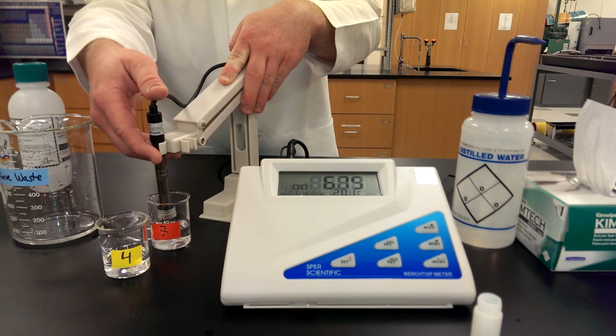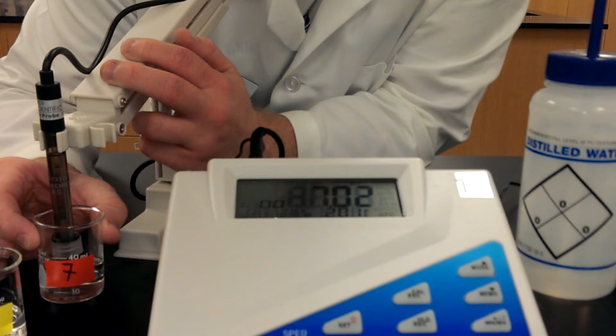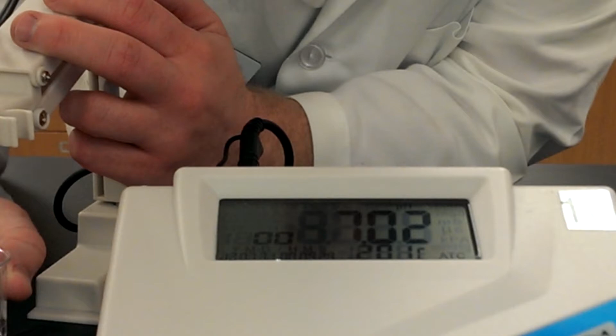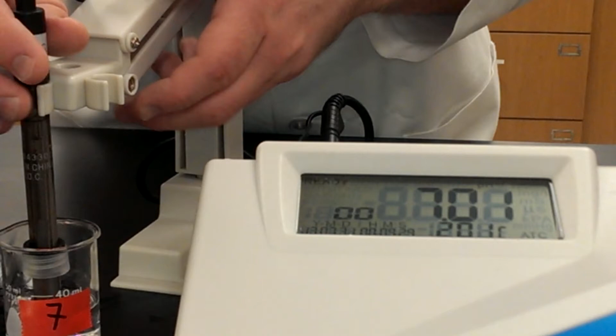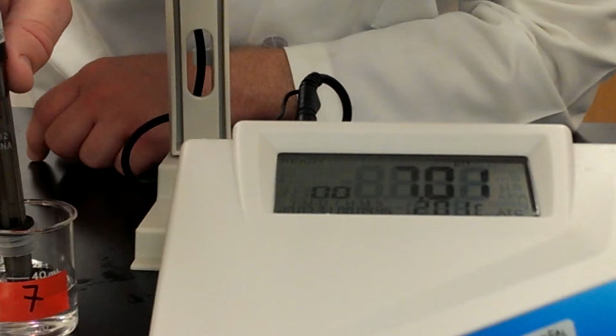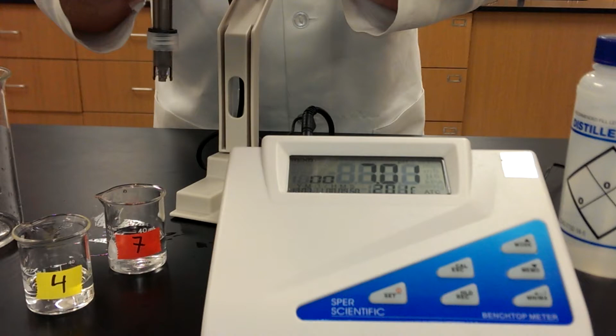And there's a couple of ways you can do this. You can swirl the beaker around and make sure you don't hit the sides of the pH probe with the beaker. You should never hear a clanking sound or a clicking sound or anything like that. You just want to make sure that the probe touches the solution only. Or you could take it off of this arm and you can swirl it around. Alright, now we can see here it's reading a 7.01, 7.02. So we're going to go ahead and calibrate this. Even though that's very close, probably doesn't need to be calibrated, we're going to go ahead and do that anyway. So we clip it back on here.